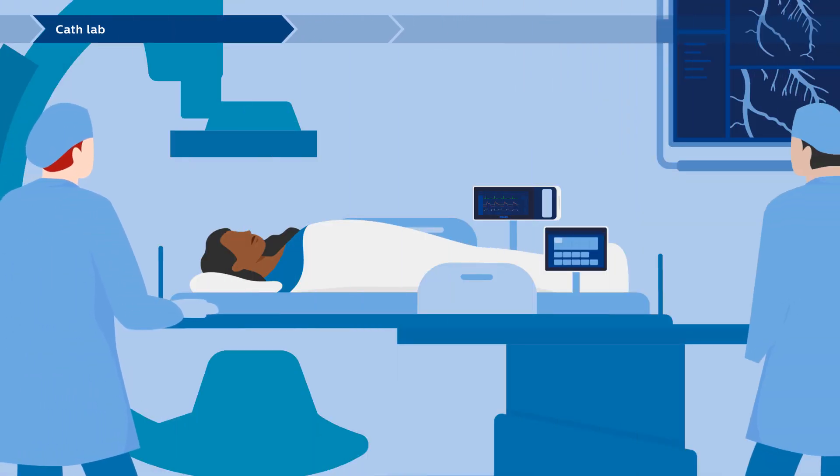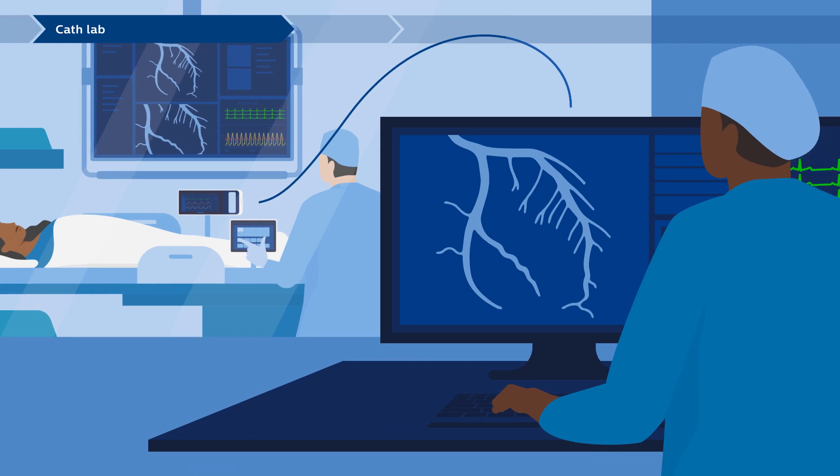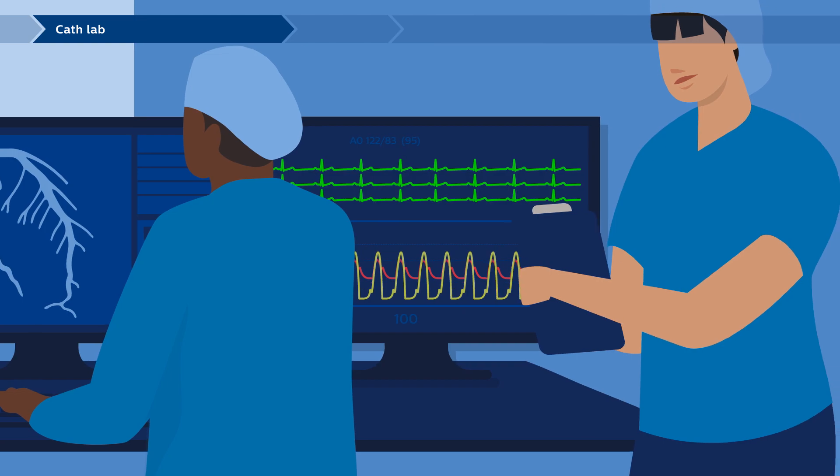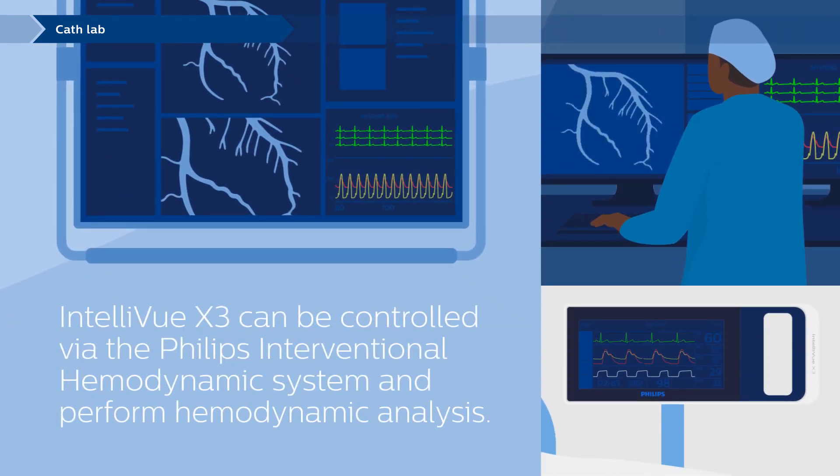Once the patient arrives in the cath lab exam room, the IntelliVue X3 is docked into the exam table docking station. Patient demographics from the X3 are exchanged with the Philips Interventional Hemodynamic System to help safeguard against manual entry errors. Real-time measurement data from the X3 is shared with the hemo system for advanced hemodynamic monitoring.